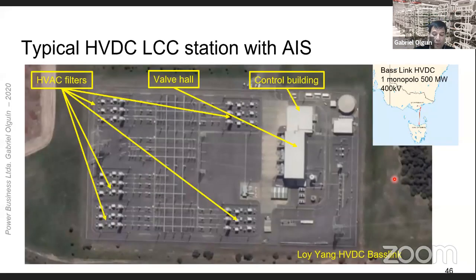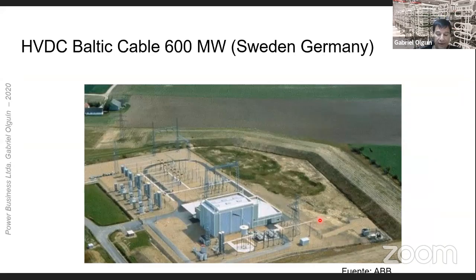This is a Google Earth top view of Loy Yang converter station in Australia. Again, it can be seen that most of the area of the converter station is HVAC equipment, while just a fraction of the area is taken by the HVDC yard. Finally, here you have a rather compact HVDC converter station. This is the Baltic Cable between Sweden and Germany. This is a monopolar converter station rated at 600 megawatts. The valve hall, the AC filters, and the HVDC yard can easily be identified.